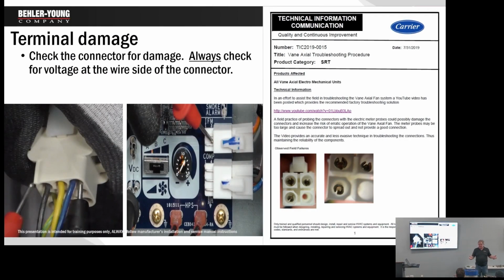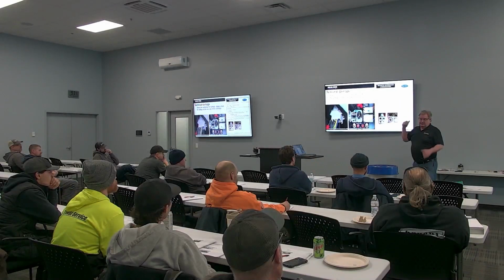Unit wouldn't come on. We just got in this line with this new blower. I'm on the phone with engineering. Dude, I got my voltage right here, just like you said. I got my 10 volts, and the motor's not running. And I have my voltage on the gray wire here. Well, guess what? It wasn't making it to the motor. So they proceeded to tell me to yank the unit, put another one on the roof, and they sent an RMA, and this went all the way back to Indy, and they tore it apart.